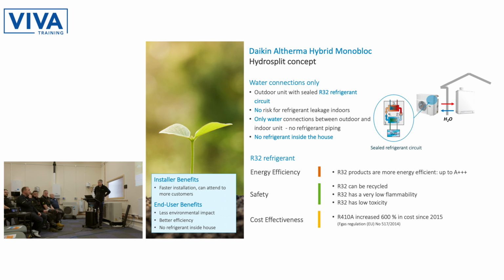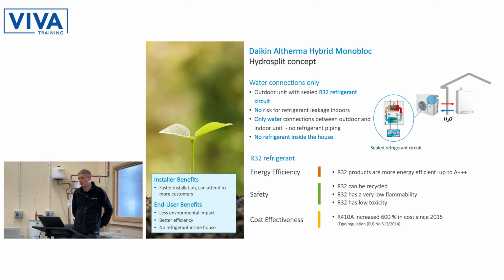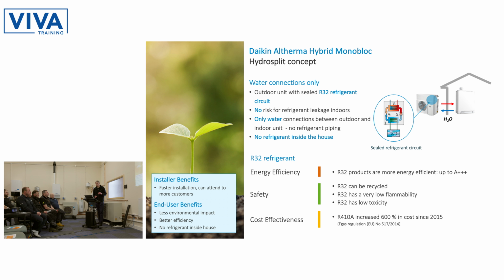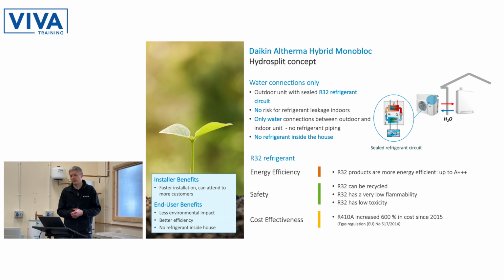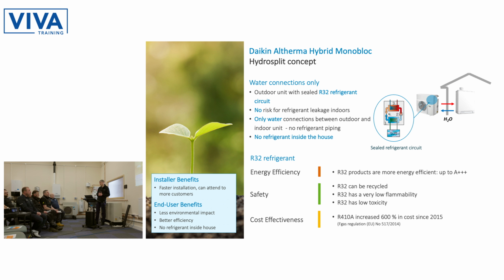Taking the hybrid to R290? Not at the moment. Obviously you've got to be careful where you install R290 in relation to a boiler and flues and things like that. You could have these quite close together either side of a wall, but you might not be able to do that with R290, so there are some limitations. So we're not driving this product down the route of R290 at the moment, but obviously who knows where it's going to develop in the future.